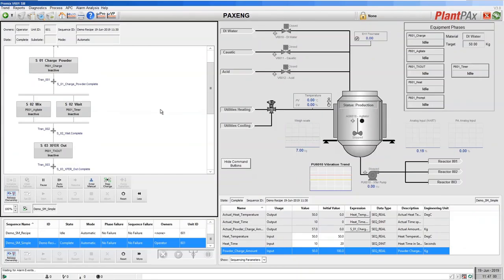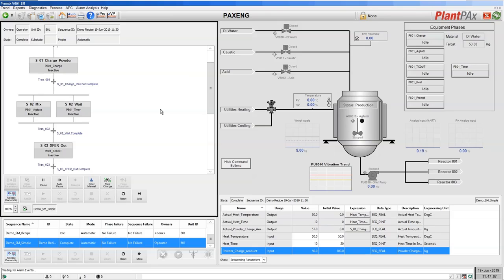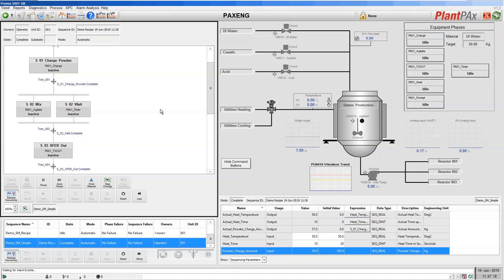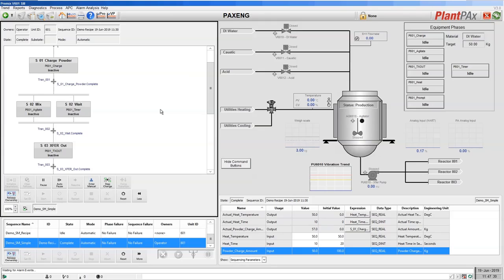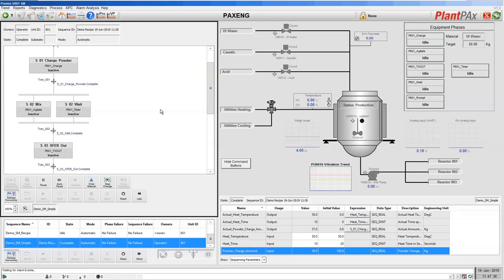Having used that free library for our control modules, the next layer in S88 is something called an equipment module. This is basically a way of simplifying a complex set of operations. For example, maybe you wish to route from one tank to another, you have a set of routing valves, you have many different routes, and you want to simplify the control. You might decide that one way of doing that is to use an equipment module where you can put it into not being used or route one, route two or route three, for example, and it controls the sequence of steps to move from one route to another. In this example, in our simple example, we don't have any complicated situations like that, so there's no need for any equipment modules.